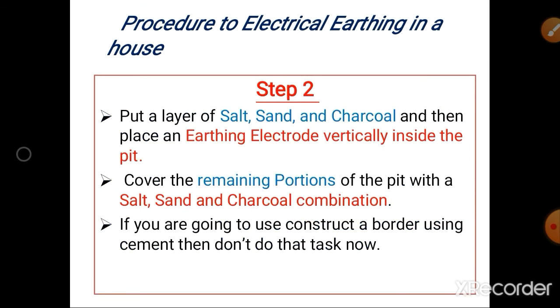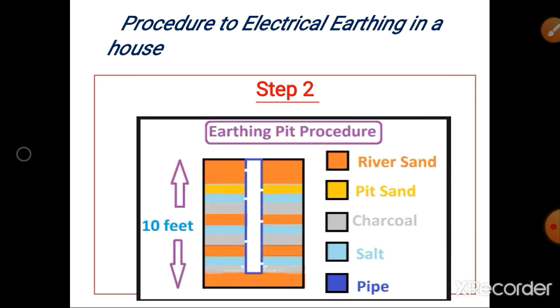Step 2: after excavating the pit, we put a 20 centimeter charcoal layer, and on that layer we place the earth pipe, the galvanized iron pipe. After placing the pipe on the 20 centimeter charcoal or sand layer, we fill the gap using alternate layers of salt, sand, and charcoal combination. Then after filling these alternate layers up to the clamp level, we pour water.